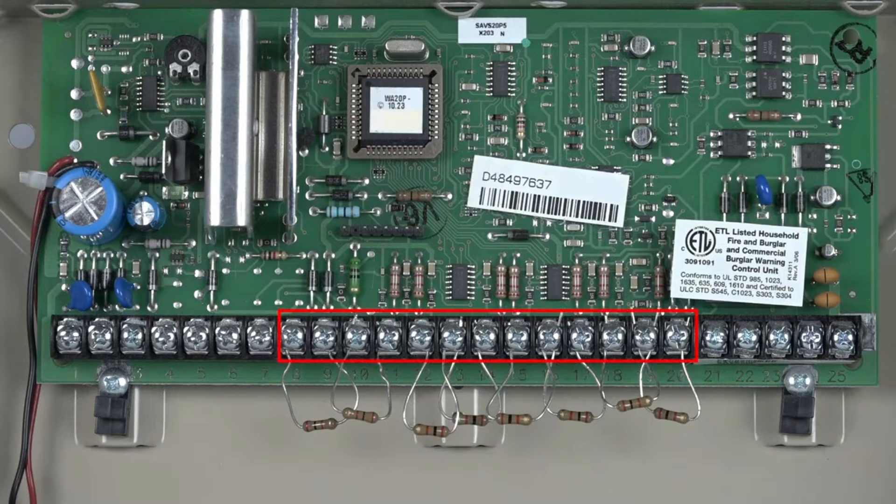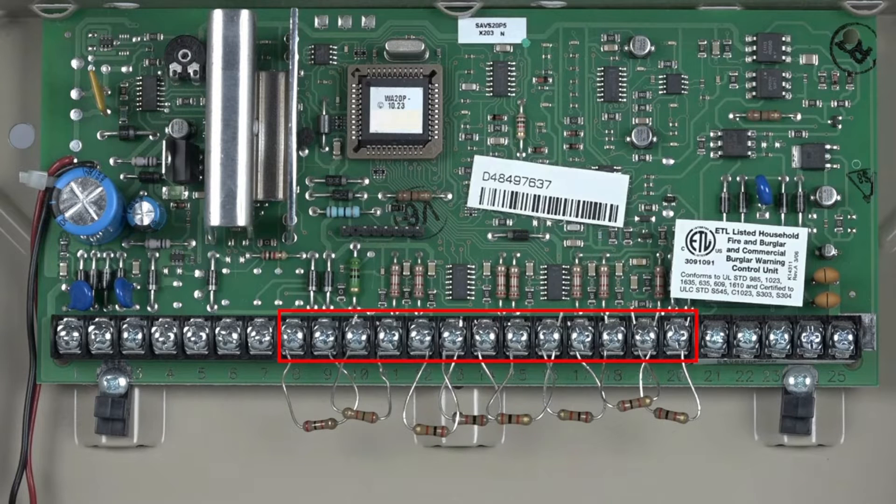Terminals 8 through 20 are your zone terminals. It is recommended to strap out these zones with 2K resistors if you are not using the zones since these have program values by default.